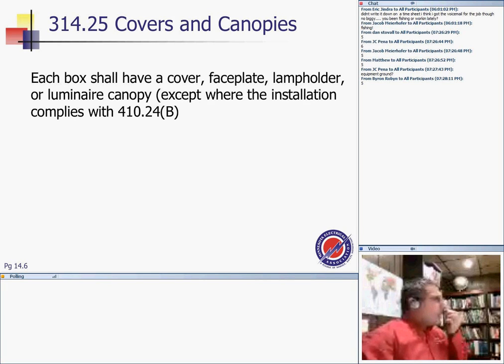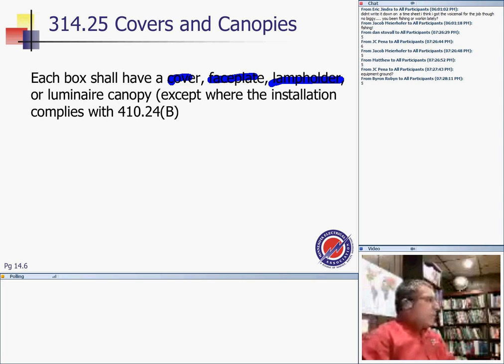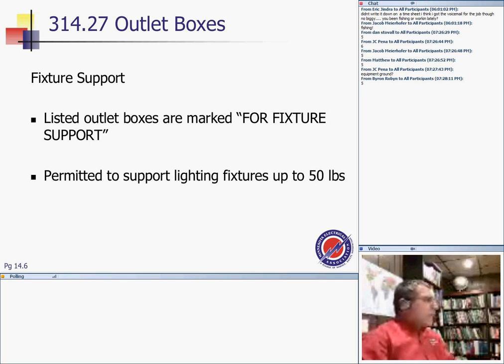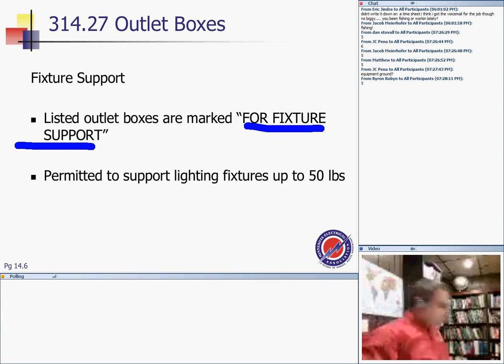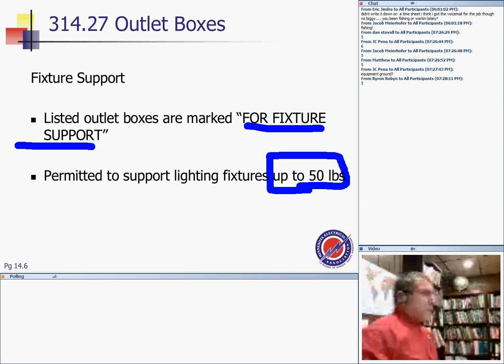Okay, we talked, guys, about covers and canopies. Each box should have a cover, a flat. The boxes have to have covers, flat, a faceplate, lamp holder, luminaire, and so on, so you can't just have the box uncovered. Fixture support. Listed outlet boxes are marked.